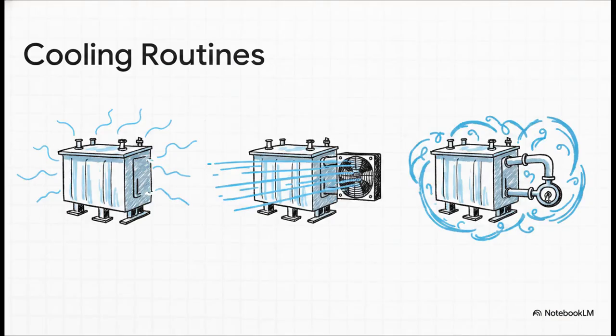Since heavy industrial plants run so incredibly hot, and heat is the ultimate enemy of efficiency, transformers absolutely need a solid cooling routine to survive. We've got a few modes here. ONAN, or Oil Natural Air Natural, is your standard mode, where oil and air just circulate naturally. It's super common for mid-sized units. Then we step it up to ONAF, where fans actually kick in to force air over the radiators as the plant load starts rising. And for heavy-duty, industrial levels, we use OFAF, Oil Forced Air Forced. That means deploying powerful pumps and giant fans for maximum cooling power.